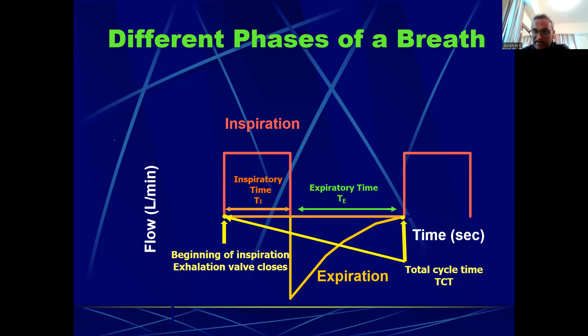Okay. Now, how does the machine give a breath? When the machine is ready to give a breath, we always think that the inspiratory valve opens. No, it is not that. Actually, when the machine gives a breath, it is the expiratory valve which closes, so that force is generated in the ventilatory circuit and the inspiration happens. So at the beginning of inspiration, the exhalation valve closes. So always think that the exhalation valve is the primary. There are no inspiratory valves. There are expiratory valves only.